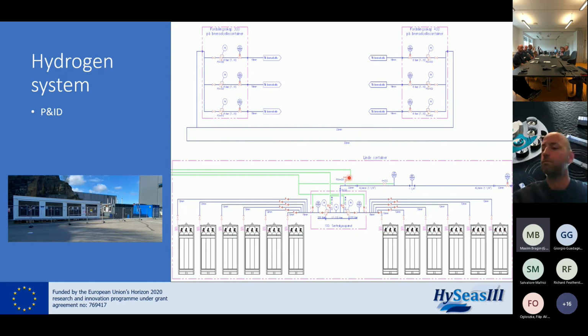I think the safety system mainly relies on hydrogen detection, so active protection. Did you have any passive protection measures like pressure drop measurements in the system or any excess flow valves implemented at all? No - that's something we experienced during commissioning and testing, that it would be beneficial to have to detect the leakages. But the leakages were so small they weren't detected by our gas sensors, which are located at the accumulating places where hydrogen can accumulate. All we had was this active prevention with the gas sensors.